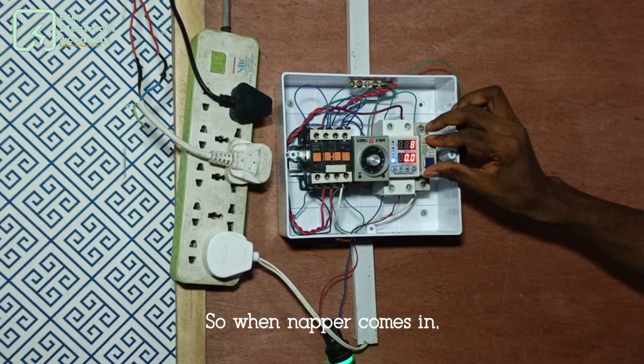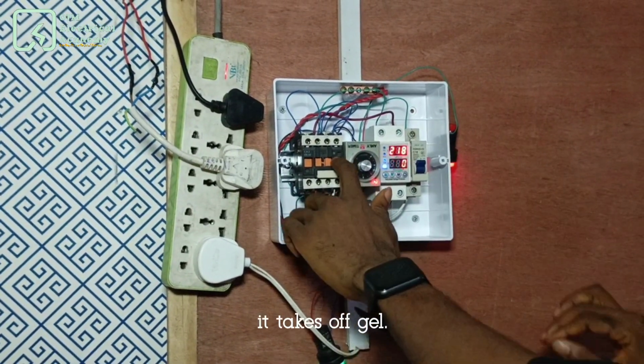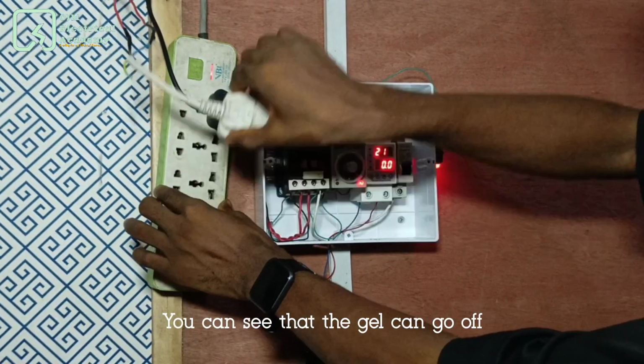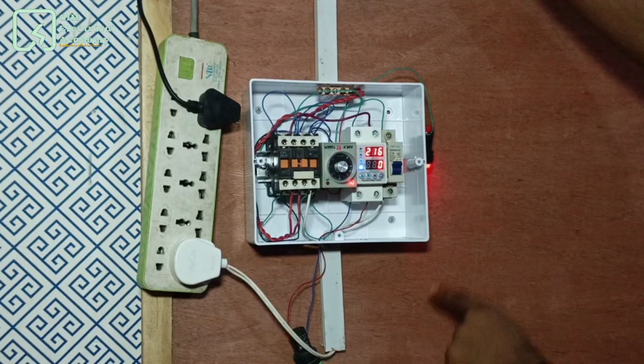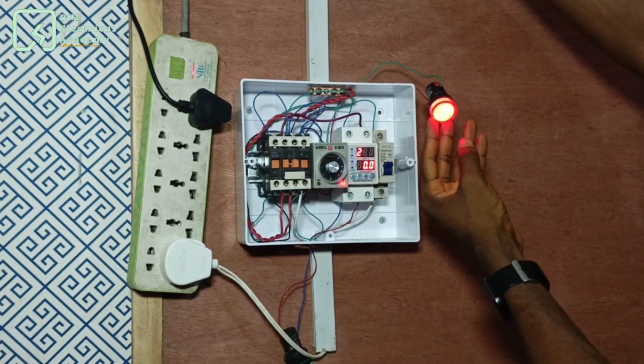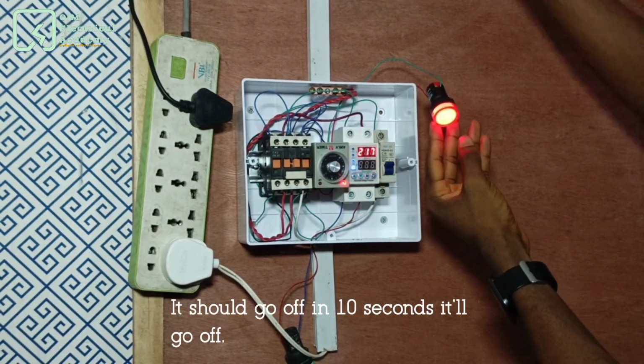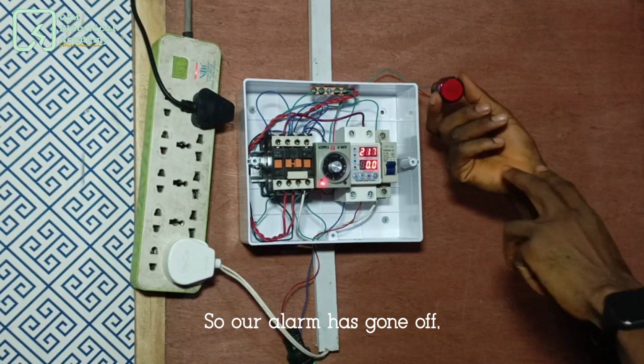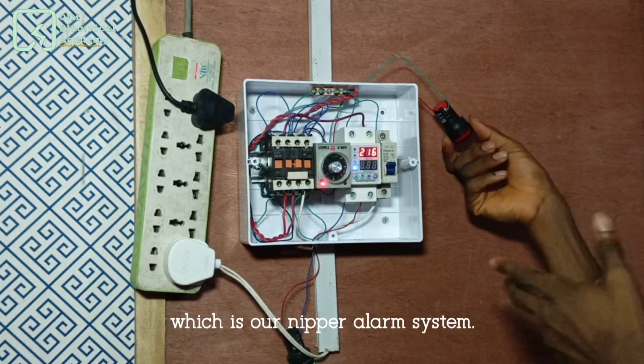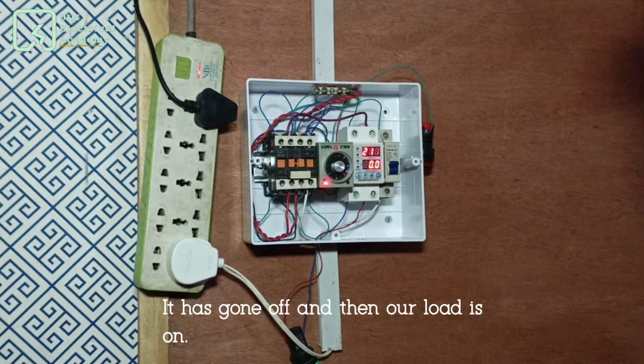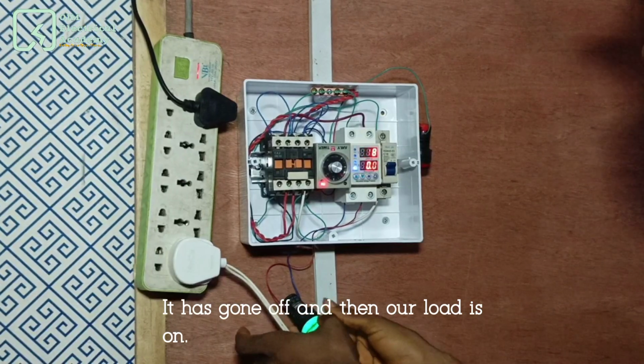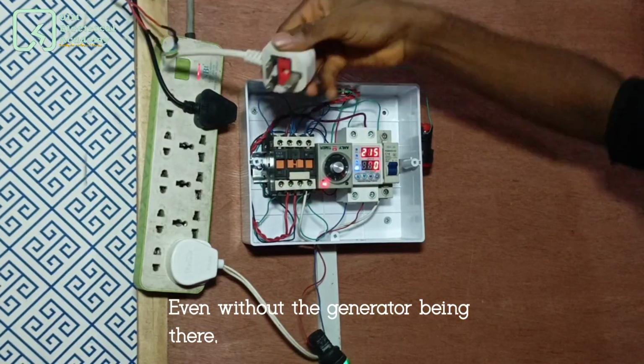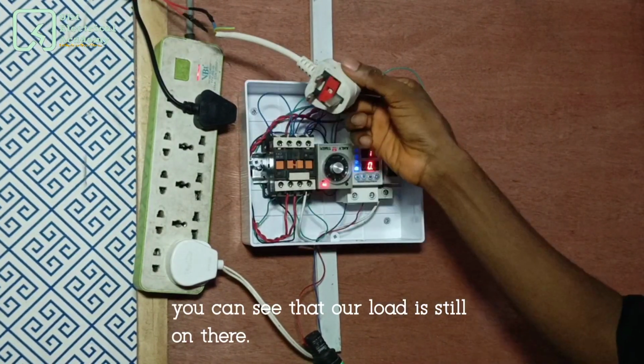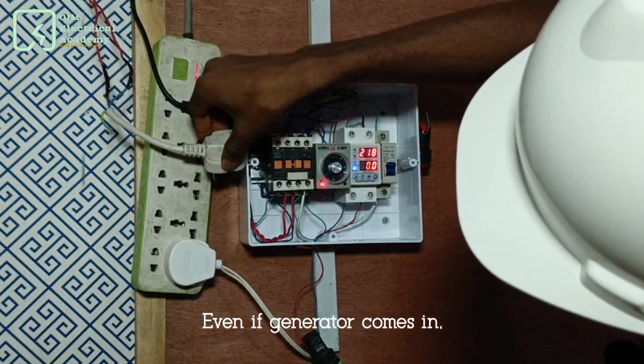So when NEPA comes in, it takes off the generator. You can see that the generator can go off and the light is still on. Then after 10 seconds, this should go off. It will go off. So our alarm, which is our NEPA alarm system, has gone off, and our load is on. Even without the generator being there, you can see that our load is still on. Then even if the generator comes in, it doesn't affect the load.